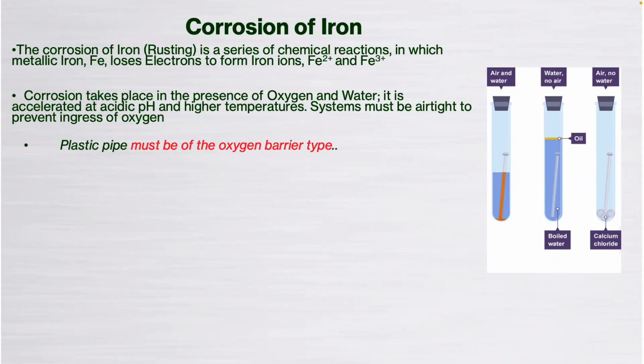Now, you may think, well, hang on, what will make the water low pH? Where would the acid come from? And that can really be through carbon dioxide, or in most cases, it comes from bacteria. If you've had a bacterial problem, maybe the system's been shut down all summer and you turn it on, areas of the system may have bacteria that will produce acid, so that could increase that.